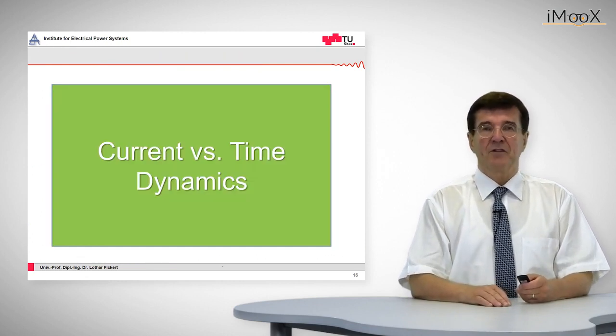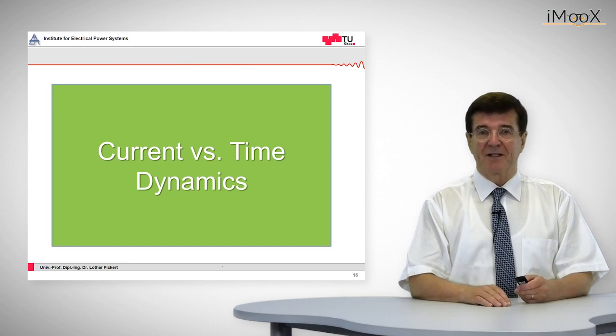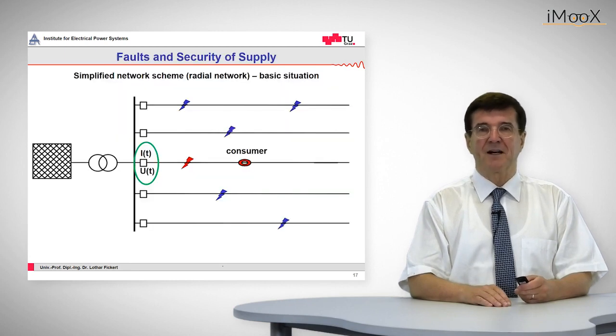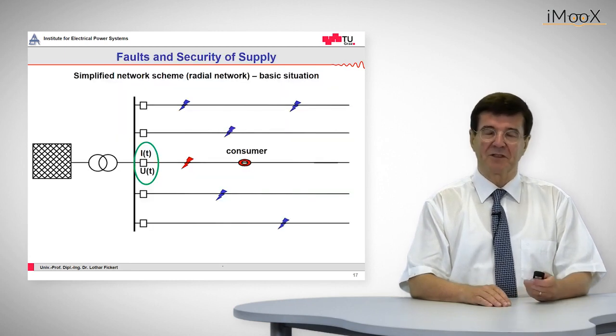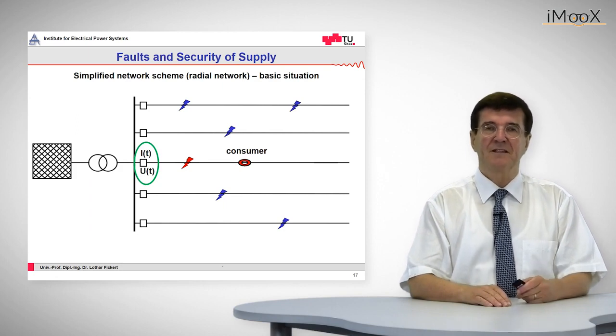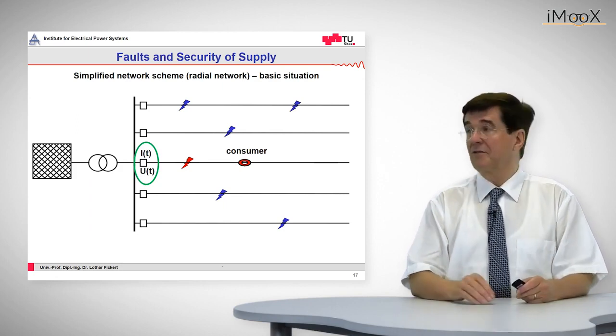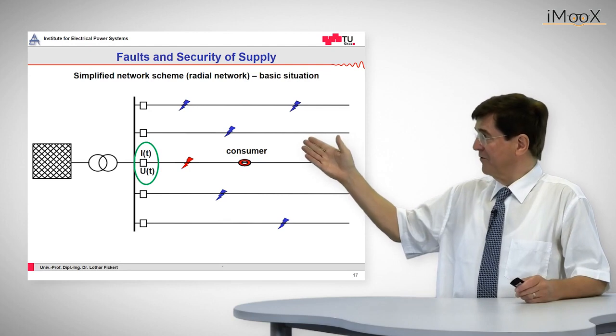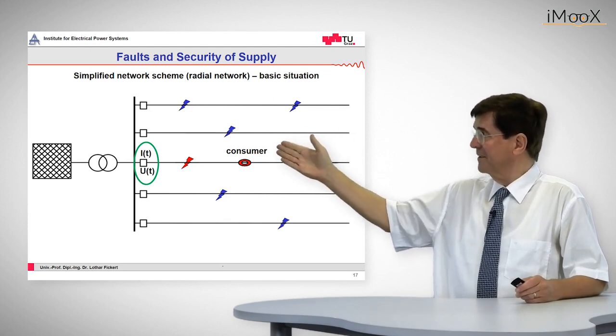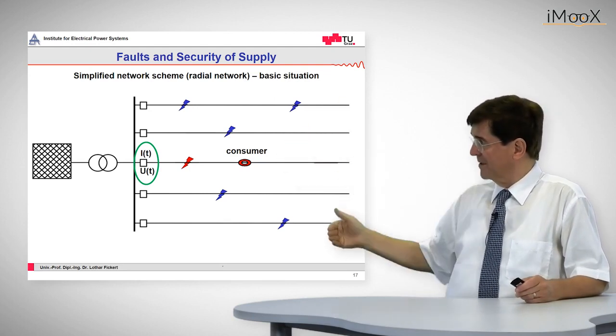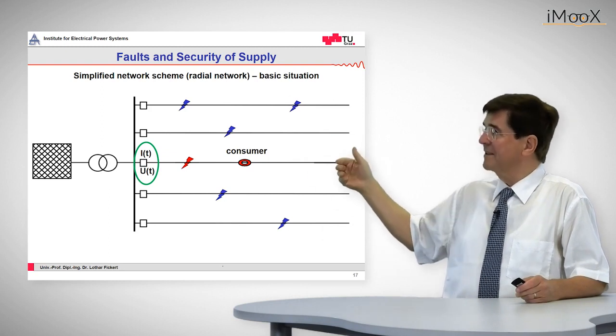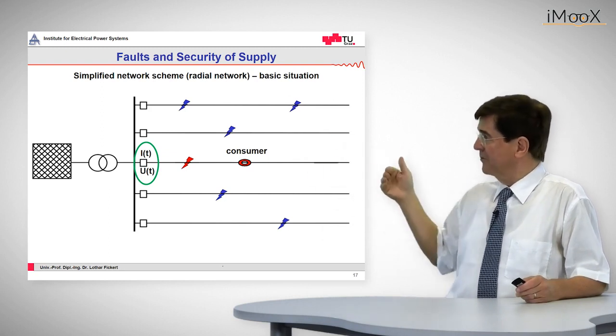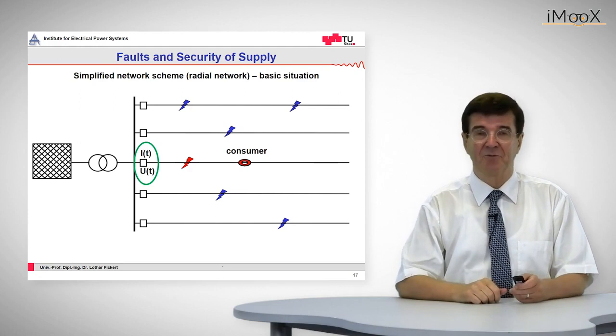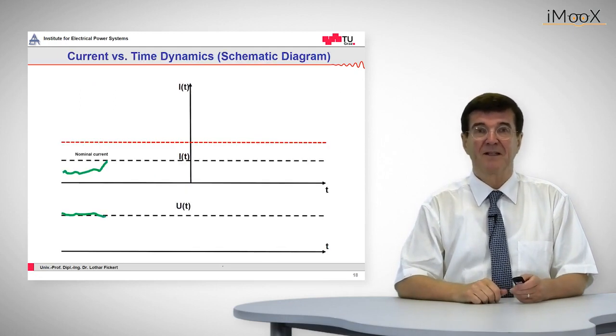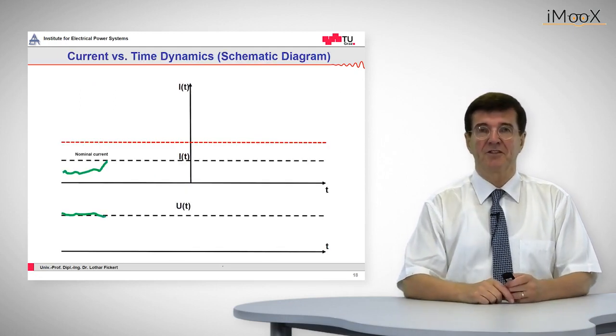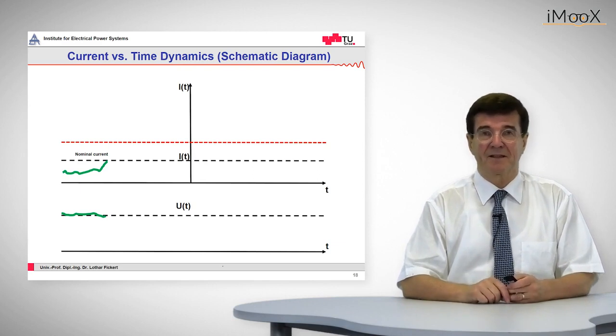So, first we look at the current versus time dynamics. Let's start with our standard grid which was already introduced. This is a radial grid. In this radial grid, from left to right, we have a grid, a transformer, a busbar, a metering device given in green, and the line with the consumer where this fault will occur. Now let's see in terms of voltages and current what happens at this moment.